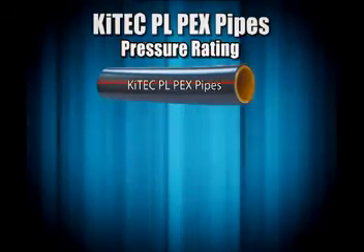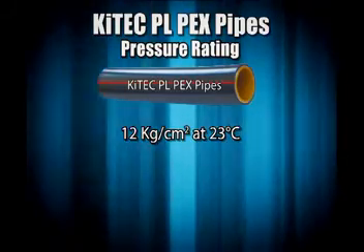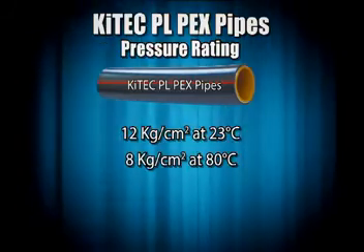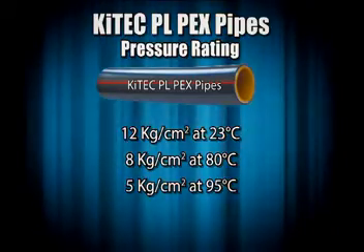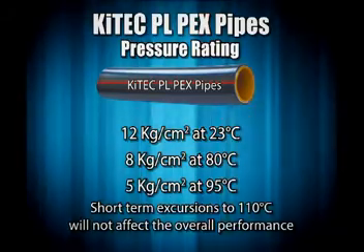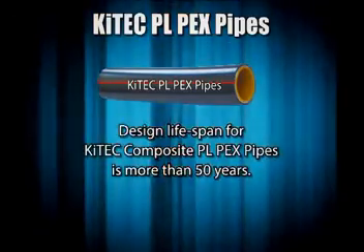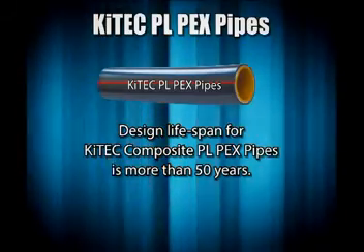KiTEC Composite PL-PEX pipes have a pressure rating of 12 kg per centimeter square at 23 degrees Celsius temperature, 8 kg per centimeter square at 80 degrees Celsius temperature, and 5 kg per centimeter square at 95 degrees Celsius temperature. Short-term excursions to 110 degrees Celsius will not affect the overall performance. Design lifespan for KiTEC Composite PL-PEX pipes is in excess of 50 years.